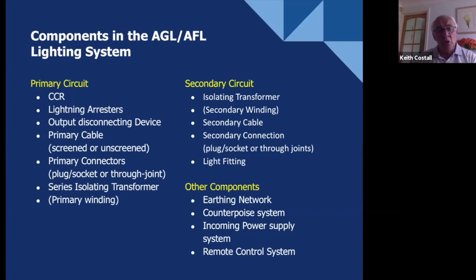And then the isolating transformer, already mentioned. The primary winding is on the primary circuit, yet the secondary winding is on the secondary circuit. And they are separated. They only connect electromagnetically. They are not connected electrically. Then we have secondary cable going out to the light fixture. For example, a transformer pit could be on the side of the runway or taxiway, which is its normal location, and it could be 30 or 40 meters to the light fixture. So we have a length of secondary cable, and then normally 2 core or 2 single cores, and that's connected to the transformer and to the light fixture with a 2-pin connector, where on the primary side, it's a single pin connector.